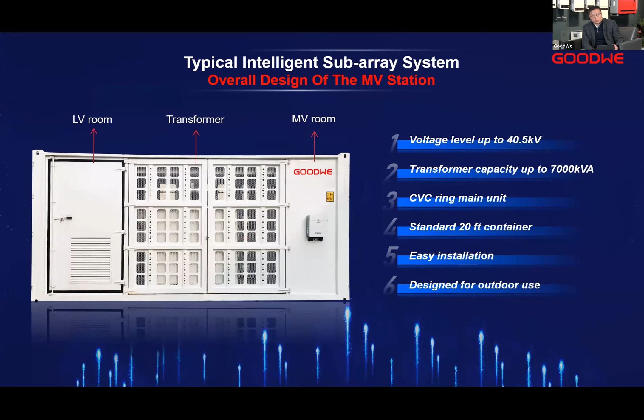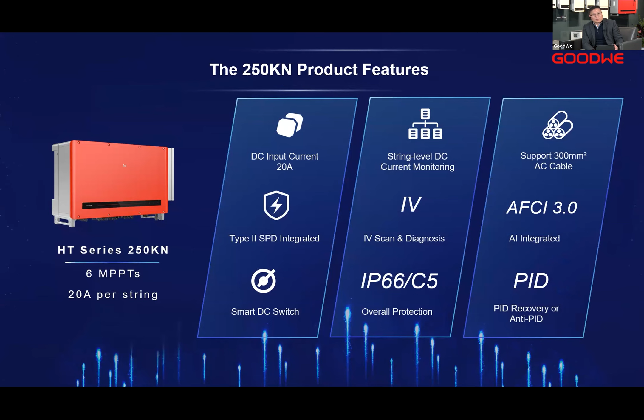Here are the main features of our 250 kilowatt string inverter: 6 MPPT with 20 ampere string current, type 2 SPD, and smart DC switch. I'll touch on more details about some of these features later. It also has string level monitoring, IV curve scanning, and generation 3 AFCI, with either PID recovery or anti-PID.